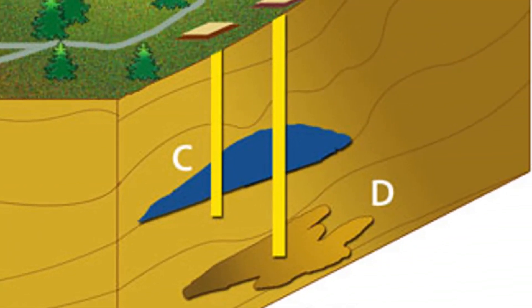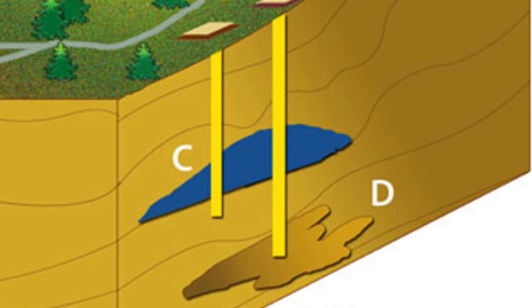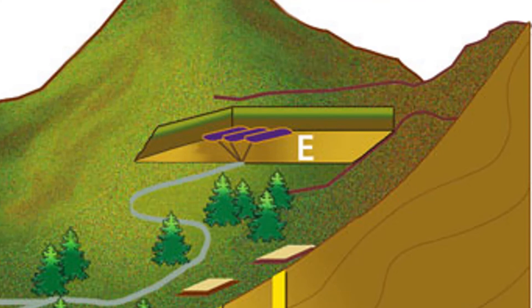C is aquifers — porous rock where you can pump gas down. The gas seeps through the porous rock and there's a layer of non-porous rock on top which prevents it leaking up to the surface. Letter D is a depleted reservoir, where oil has been pumped out of the ground in the past, leaving an empty space that is perfect for storing gas. Finally, letter E is a hard rock cavern — empty spaces within non-porous hard rock where we can pump gas up to high pressures.